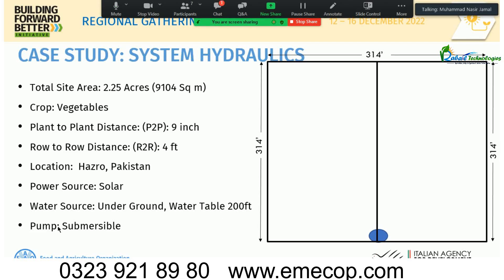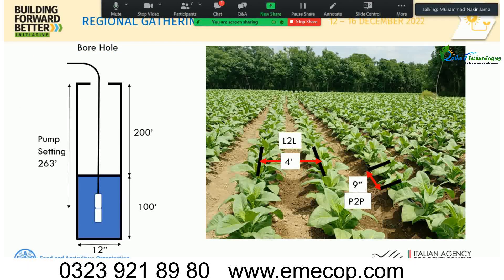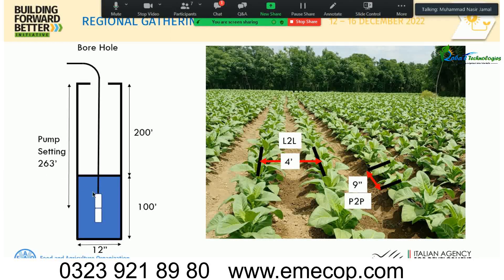The power source is solar and the water source is underground. The water table depth is 200 feet, and the pump is a submersible type. The borehole is 300 feet total with a water column of about 100 feet. The pump is set at 263 feet — about 63 feet within the water column — due to high drawdown and poor aquifer yield, to avoid dry running of the pump.